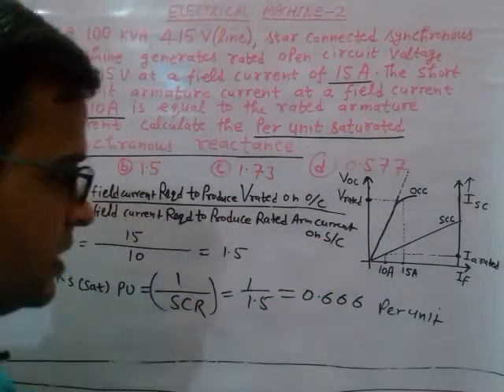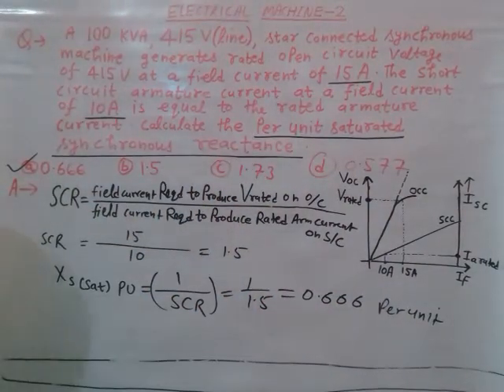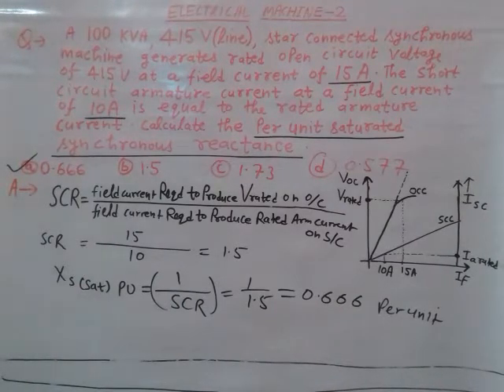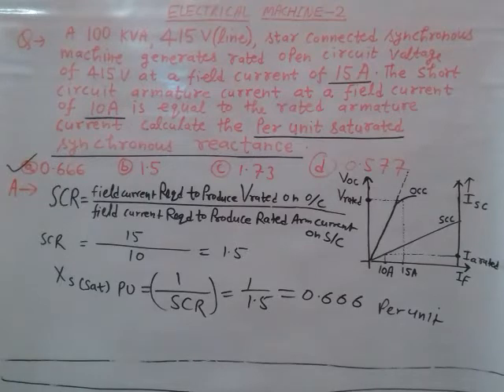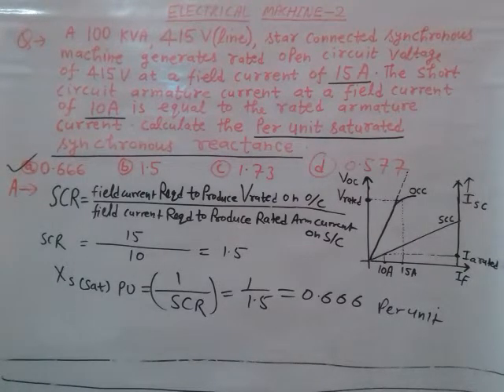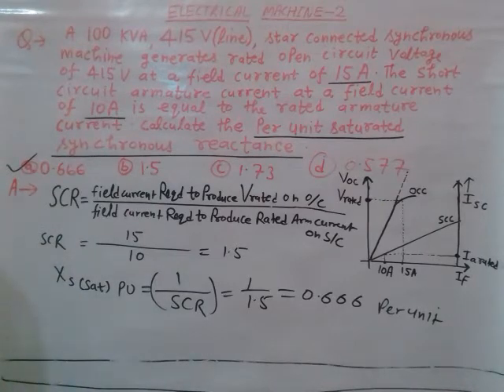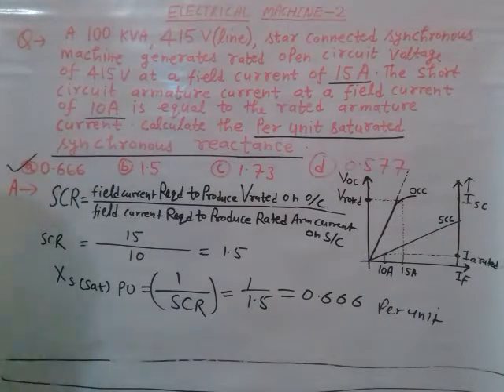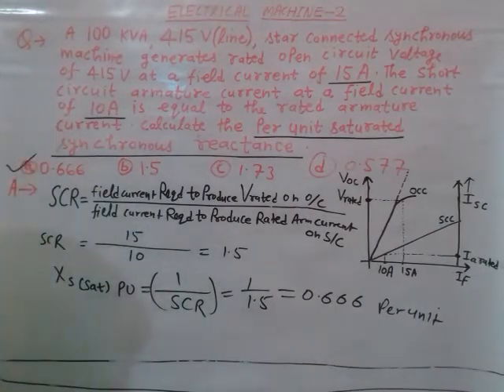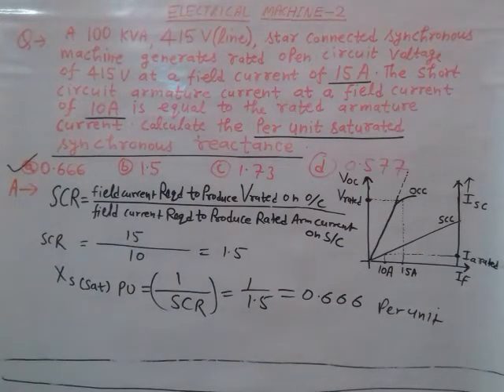Normally, in the case of turbo alternators, the value of SCR is in the range of 0.45 to 0.9. In the case of hydro alternators, the short circuit ratio SCR may be in the range of 1 to 1.5. Since SCR is a ratio it is a dimensionless number, and higher SCR means the machine will be more transiently stable.